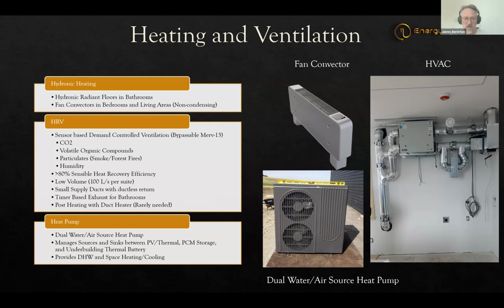We have a specially designed heat pump, shown in the bottom left. It's a dual water-air source, custom modified in the factory. We can use the solar to inject directly into the heat pump's refrigerant cycle and improve its performance. We're just now in the process of commissioning that unit in its dual mode, which also allows us to inject and extract heat from our other energy storages.